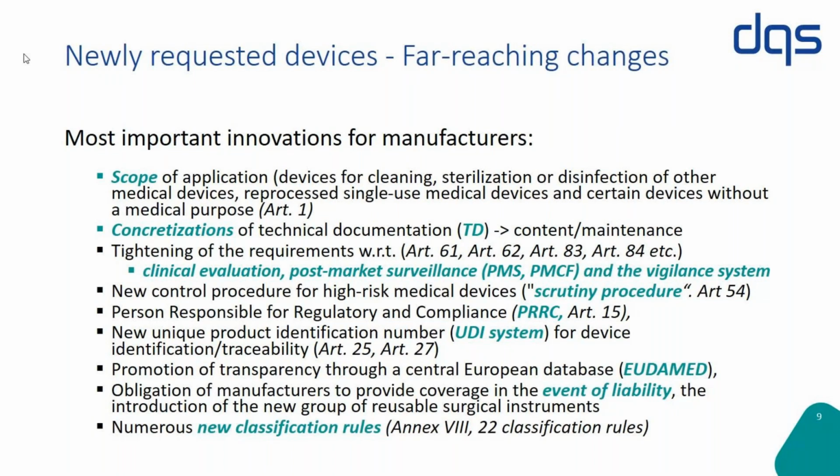If you have a device certified under the old directives, it has specific rules, but these rules do not apply without any respect to the new MDR classification rules. So take a closer look. There are new rules, there are more rules, and they are more specific. So this is one big obstacle we every time see when we have a new application by a client, that these new classification rules are not that easy to fulfill, to define your product as it was under the old directives.